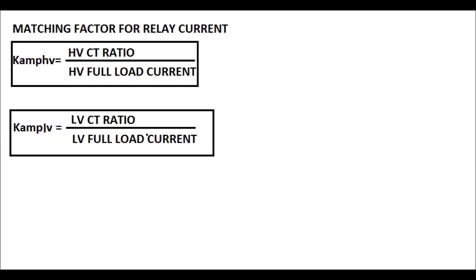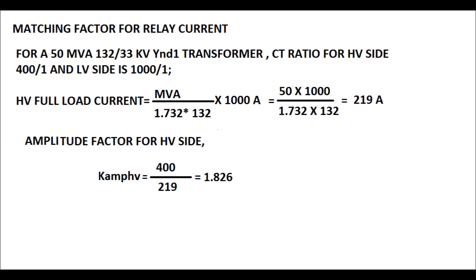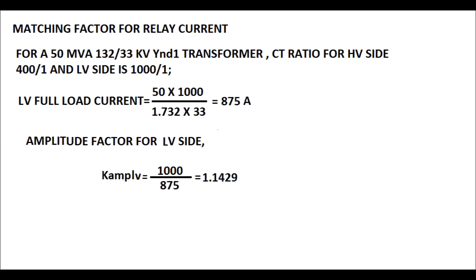The matching factors for relay current are: for the HV side, Kamp_HV equals the HV CT ratio divided by the HV full load current; for the LV side, Kamp_LV equals the LV CT ratio divided by the LV full load current. For example, for a 50MVA, 132/33kV power transformer, the CT ratio for the HV side is 400/1 and the LV side is 1000/1. The HV full load current is 219A. Therefore, the amplitude matching factor for the HV side is Kamp_HV = 400/219, which equals 1.826. The matching factor for the LV side is Kamp_LV = 1000/875, which equals 1.1429.